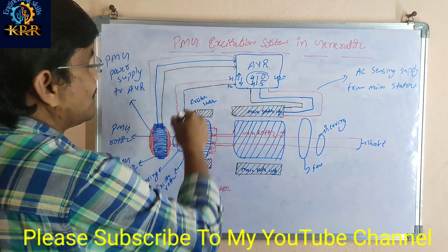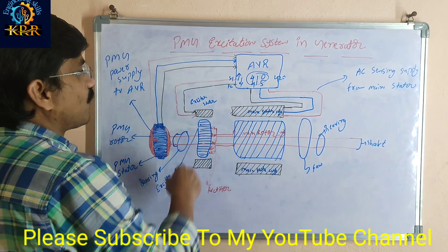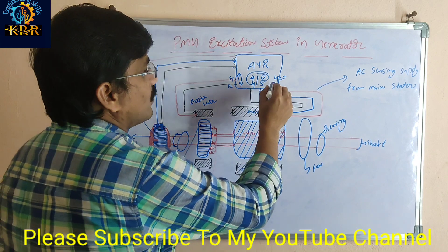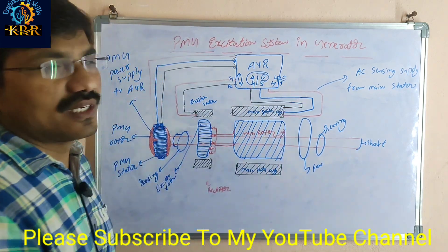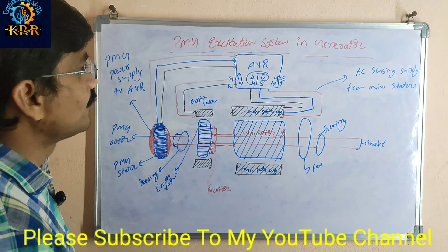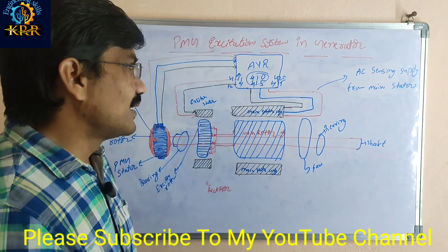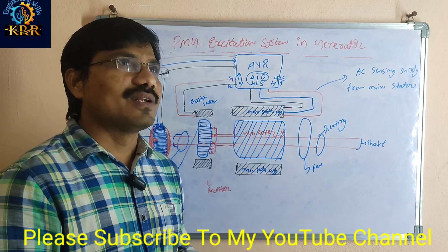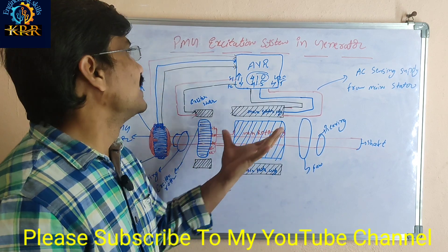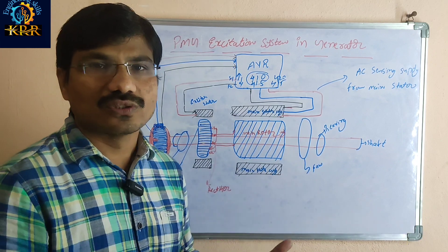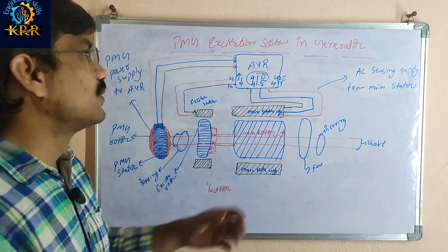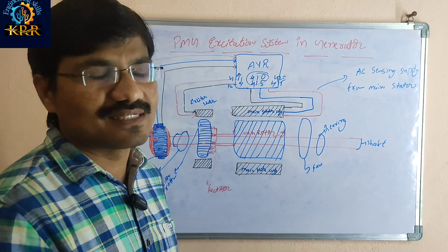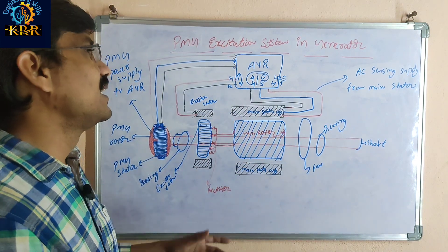After the voltage reaches 415 volts, if it rises further to 420 volts, the AVR reduces excitation — under-excitation — meaning low power is given, low flux is generated, and the final output voltage is reduced back to 415 volts. Finally, both the self-excitation system and the PMG excitation system are mainly used in generators.